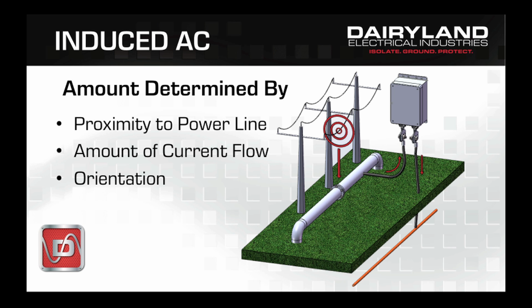Another big problem that's actually of growing concern for pipeline operators is induced AC that gets coupled into a pipeline due to the fact that it's located close to a major AC power source. Generally speaking, it's because the pipeline is sharing corridors with overhead power lines.